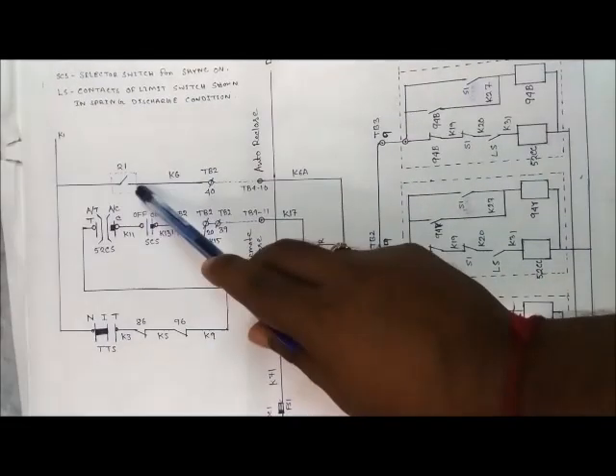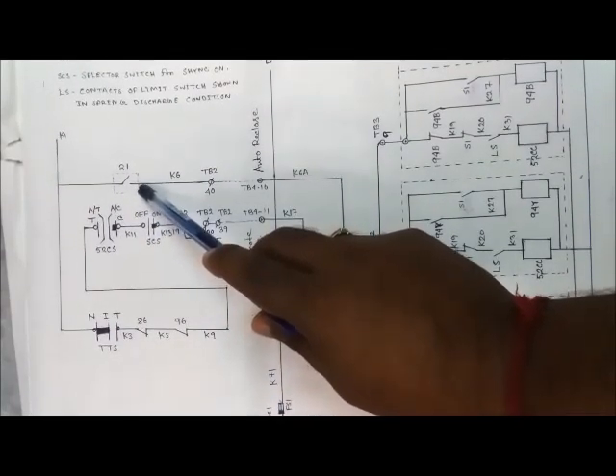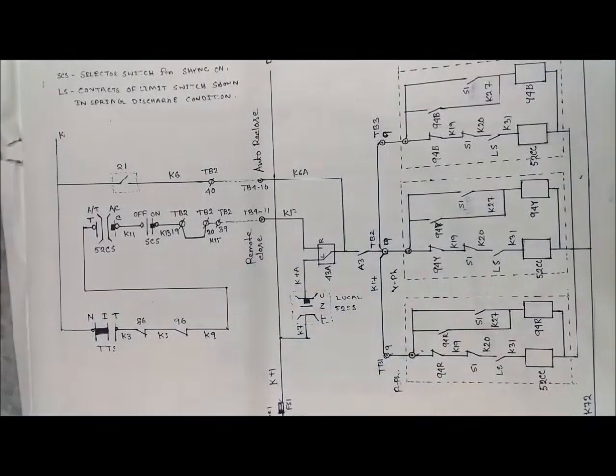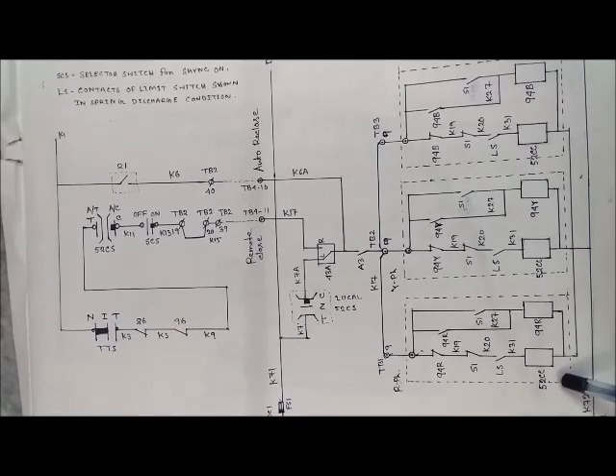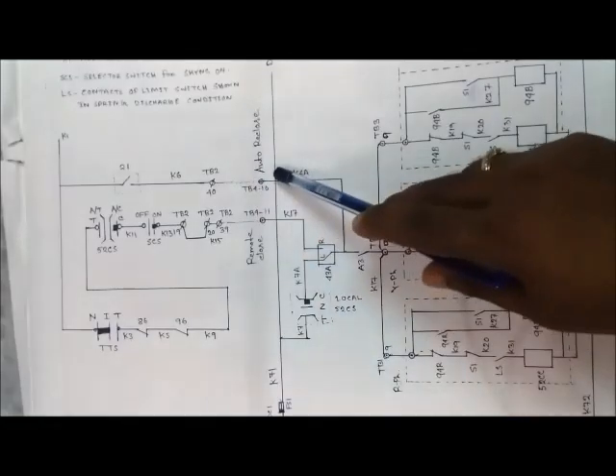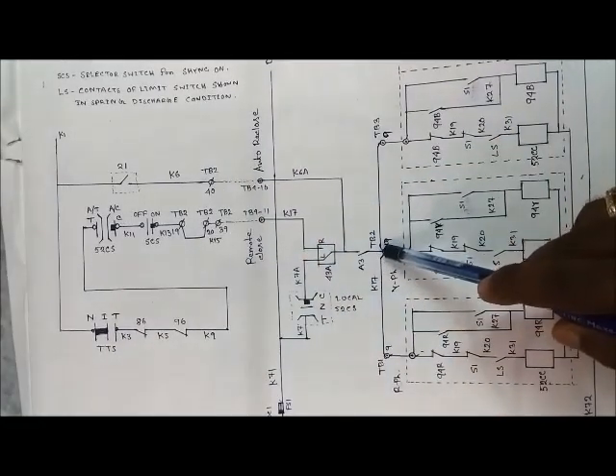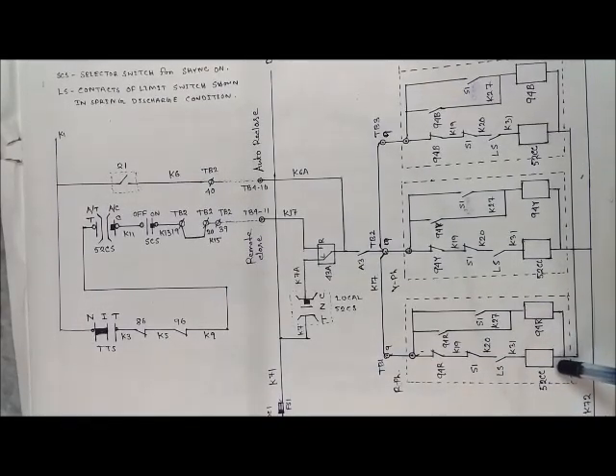Contact 21 is for auto-reclose in a transient fault. If a single-phase tripping occurs — for example, the R phase pole opens in a transient fault — after a dead time of 600 milliseconds for a 220kV circuit breaker, this contact will close from the distance relay. The positive DC comes through this part to the common terminal and through the closing coil of the R phase, turning ON the R phase pole. This is the function of the auto-reclose.